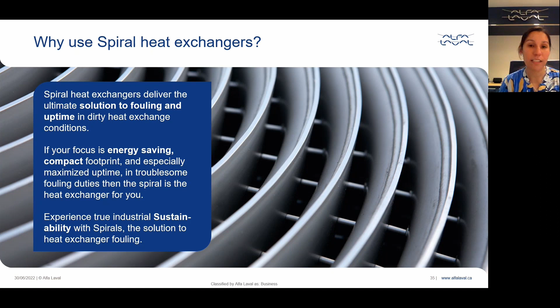The spiral heat exchanger is very unique because it has the ability to provide self-cleaning of the internal channels. This is a very important feature for very fouling media. The way it works is the moment that fouling starts to occur, there is a reduction in the cross-section area, and buildup starts inside the channel of the spiral. This buildup will increase the local velocity and also the shear stress in that localized section. Shear stress provides shear forces that will actively remove the deposit of fouling and push it outside the heat exchanger. That is the way the self-clean feature works and performs inside the spiral.